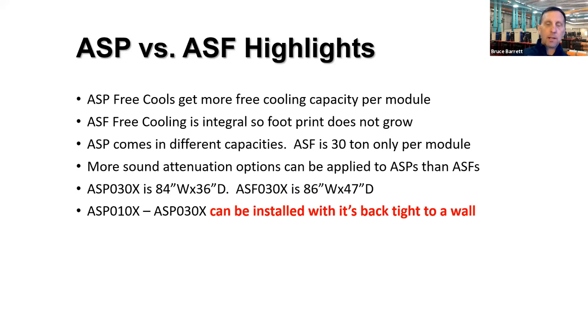So I mentioned ASP modular, ASF modular. ASP free cools do get more free cooling capacity, but they have a longer footprint. The ASFs with integral free cooling have a very, very tight footprint. We're doing a lot of 60, 90 ton air cooled jobs with integral free cooling for these small data centers, small office buildings. They have a 10 by 10 room that has a 60, 80 ton load. It's a tremendous amount of load for these data closet or data rooms. More sound attenuating options can be applied to these modular chillers to get where you need to be. Give us the requirement at the lot line or the requirement for the property, and we can try and develop the minimum needed to meet those sound levels.